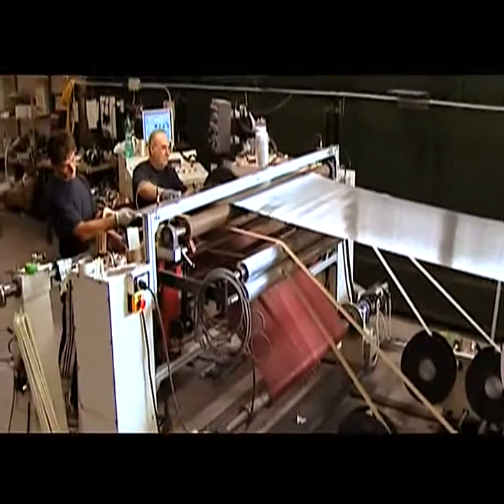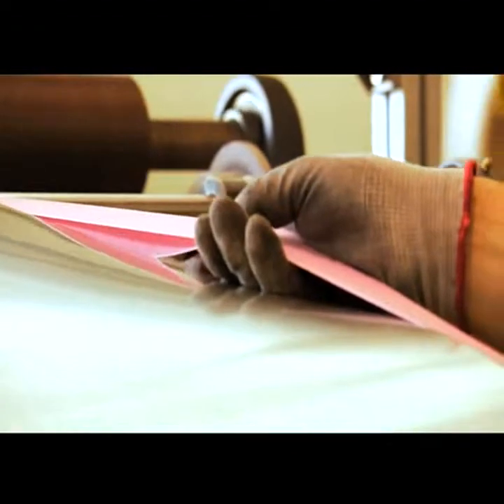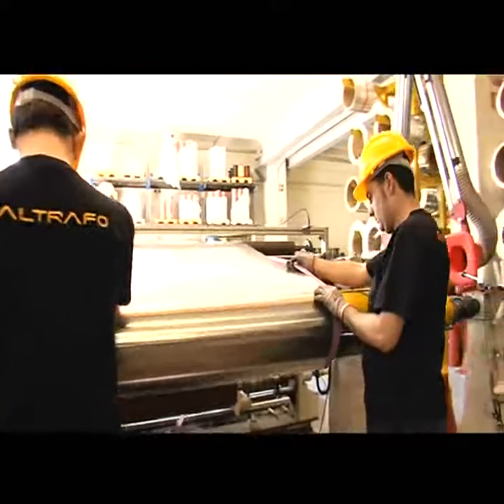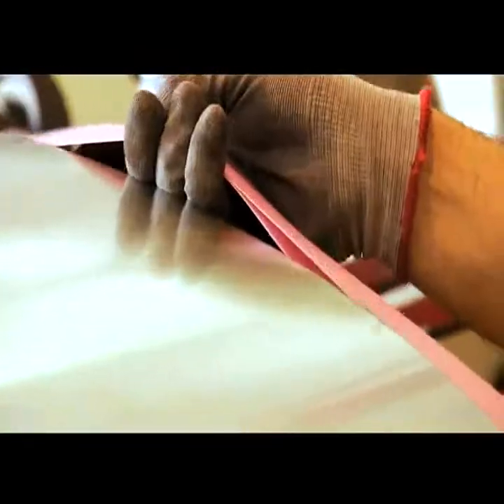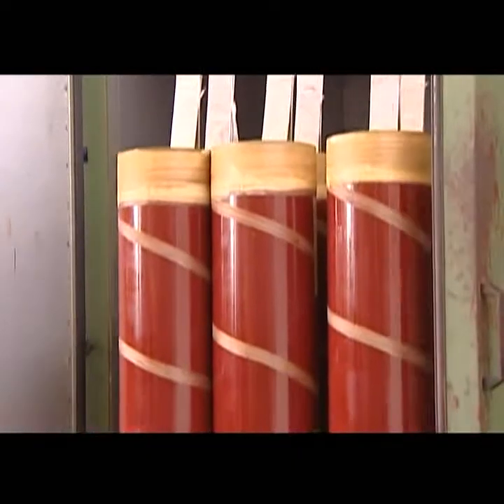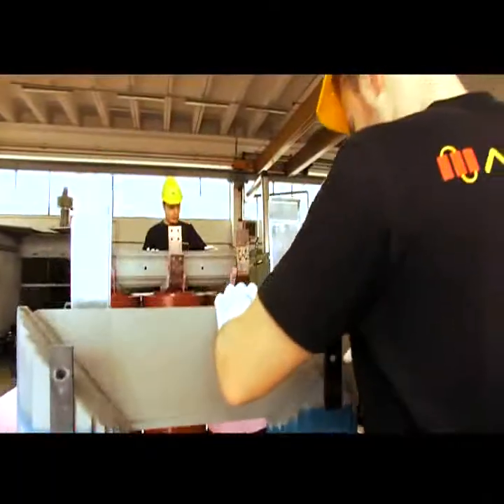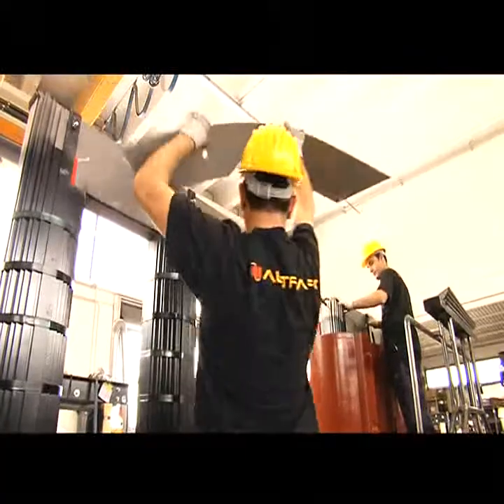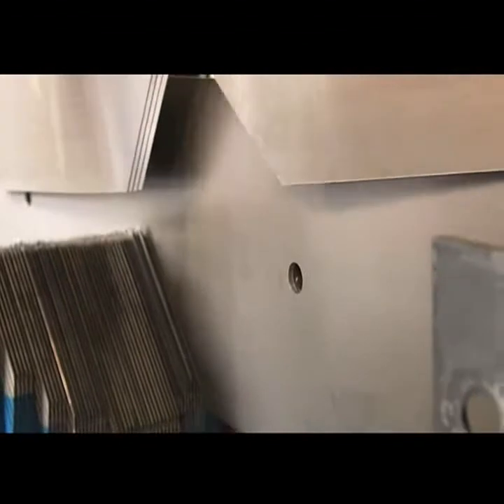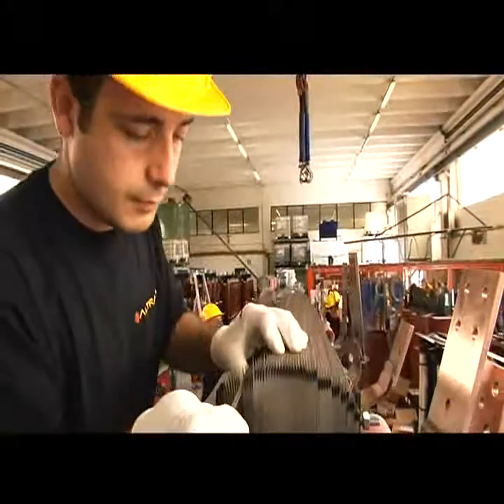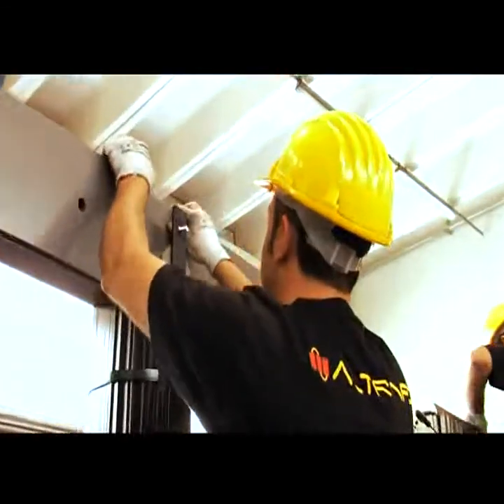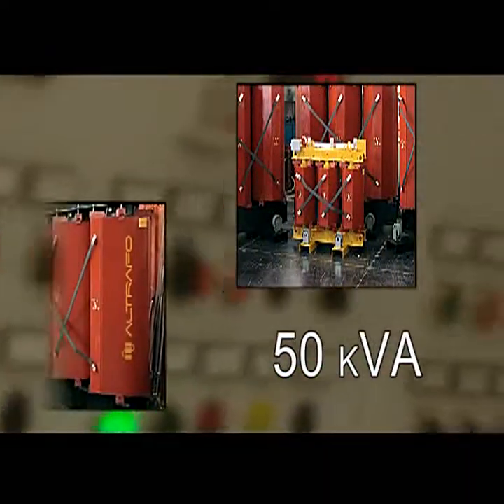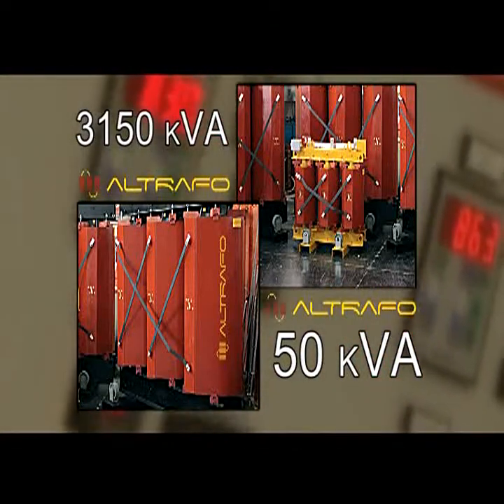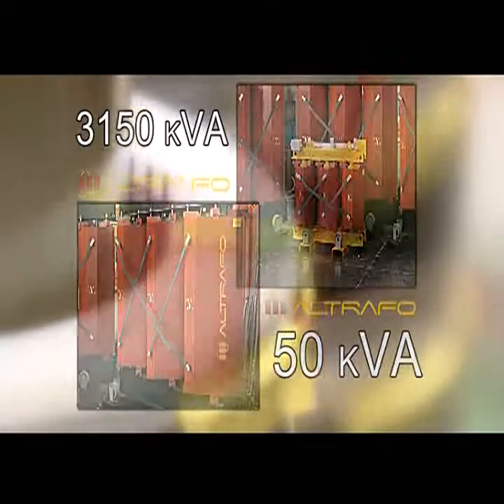Low voltage windings are realized in aluminium or copper plate. Differently from the medium voltage windings, the low voltage ones are impregnated in electro-insulating varnishes and then desiccated in furnace. The magnetic core is made of grain-oriented ferrosilicon sheets and cut to 45 degrees step-lap. ALTRAFO selects different types according to customer requests, to normal or low values of losses. ALTRAFO supplies transformers whose standard range goes from 50 kVA to 3150 kVA and voltage up to 36 kV insulation class.